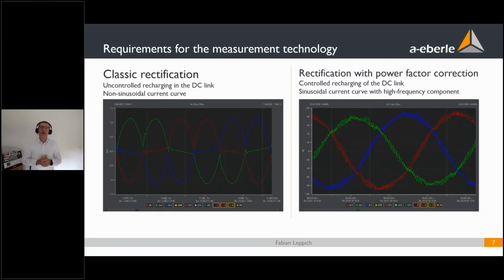On our hand side, we get new requirements for measurement technology due to new consumers and new technologies for production. In the past, it was always the so-called classic rectification. We have, for example, a B6 rectifier which brings AC to DC with an uncontrolled recharging in the DC link. You can see here on the left-hand side, the sine wave normally looks like that - 10 milliseconds, again 10 milliseconds, then 20 milliseconds. This B6 rectifier has an uncontrolled recharging of the DC link, and this produces the odd harmonics.